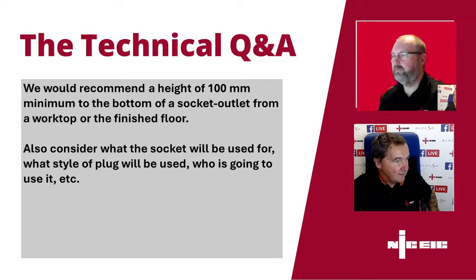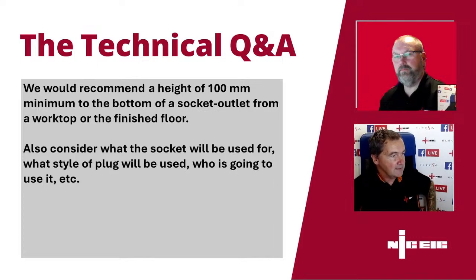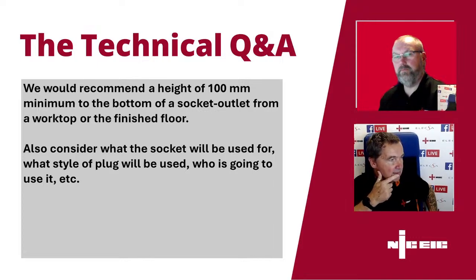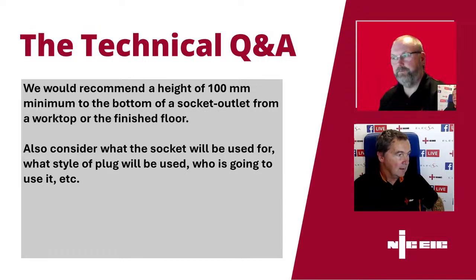I think the same engineer asked, shouldn't life safety systems, fire alarms, have separate containment, not using a system designed for bracketry? This might be thanks to the engineer that asked about using Unistrut for containment. One thing is that if you do have containment with both safety services and non-safety services, then they should be segregated and labelled accordingly, so that people know that when installing, they're not going to damage the safety services by installing a non-safety related cable into that common trunking. So they should be partitioned.